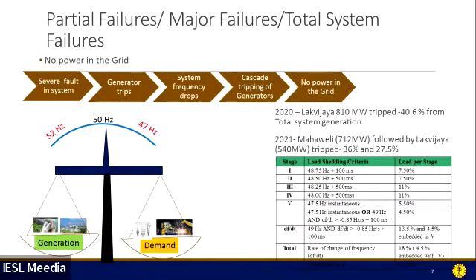So how does it happen? Total system failure means no power in the grid. We have to have a severe fault, and in response a generator can trip. Definitely, when the generation trips, system frequency drops. When it drops further and reaches the under-frequency trip settings, or protection settings, of the generators, they will trip as a cascading event, and ultimately there is no power in the grid.